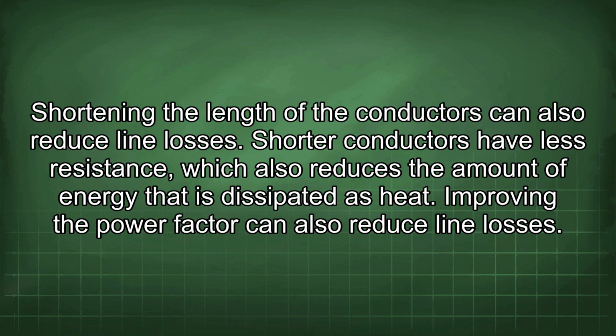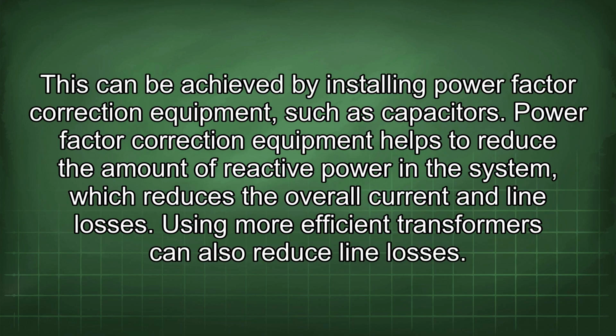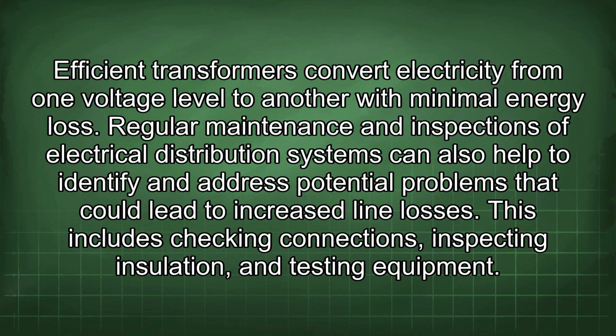Improving the power factor can also reduce line losses. This can be achieved by installing power factor correction equipment such as capacitors. Power factor correction equipment helps to reduce the amount of reactive power in the system, which reduces the overall current and line losses. Using more efficient transformers can also reduce line losses. Efficient transformers convert electricity from one voltage level to another with minimal energy loss. Regular maintenance and inspections of electrical distribution systems can also help to identify and address potential problems that could lead to increased line losses. This includes checking connections, inspecting insulation, and testing equipment.